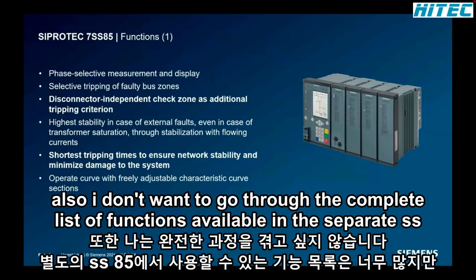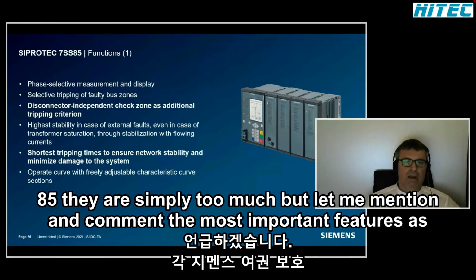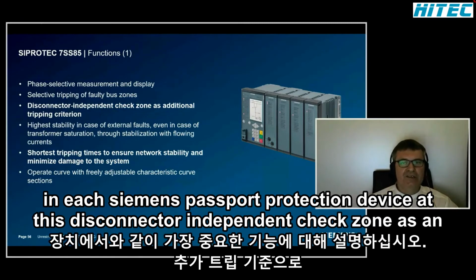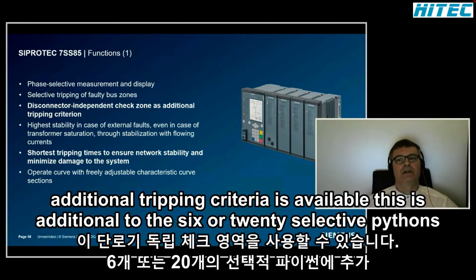Also, I don't want to go through the complete list of functions available in the 7SS85. They are simply too much. But let me mention and comment the most important features. As in each Siemens busbar protection device, a disconnector independent check zone as an additional tripping criteria is available. This is additional to the 6 or 20 selective bus zones.